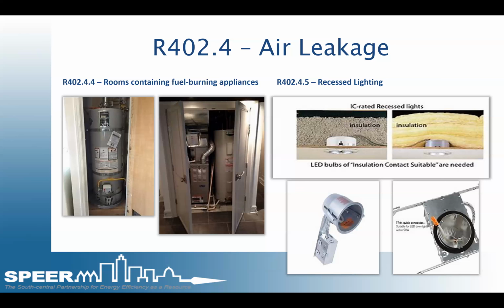The door to that room must be weather stripped, and a threshold at the bottom of that door must be sealed and closed. So a lot of this stuff seems self-explanatory, but trust me, it does happen in the field, and it has happened to me from a large volume builder. No one caught it on design and no one caught it on permit documents. And this is a very big health and safety issue. It was poorly designed really, but it could be mitigated if it was excluded from the conditioned space. So it's a health and safety thing that the energy code kind of blends into with other health and safety issues.